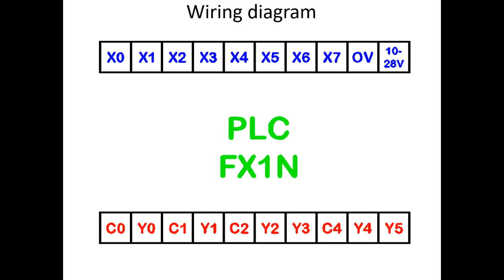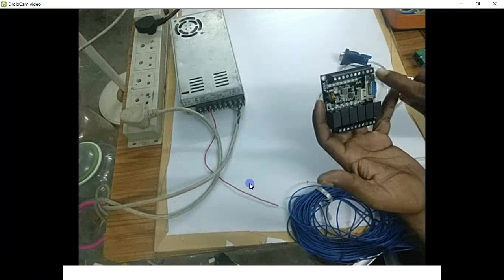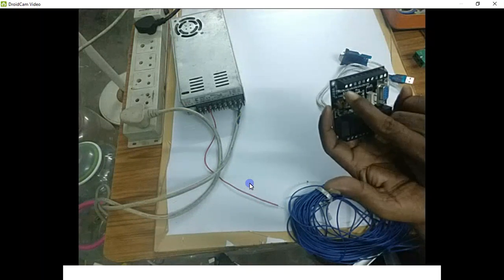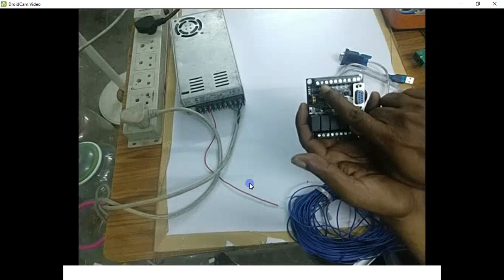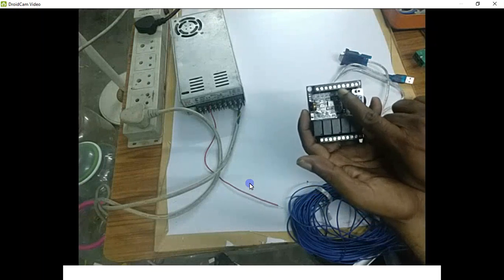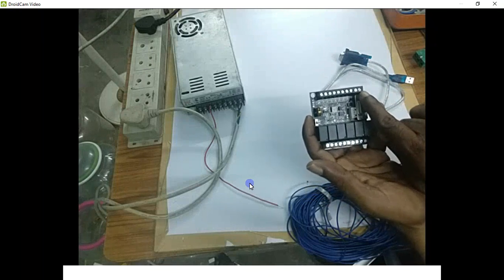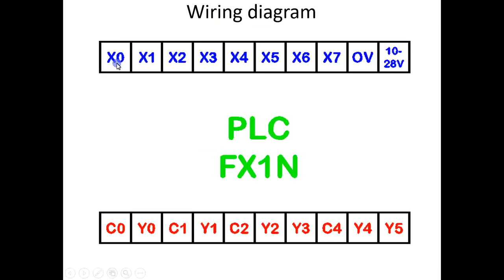This is the wiring diagram of this particular board. On this side you have 10 screw points: X0, X1, X2, X3, X4, X5, X6, X7, plus the power supply points — 0 volt and either 12 volt or 24 volt. That is what is mentioned here. This is specifically for the PLC FX1N, which accepts 10 to 28 volt.